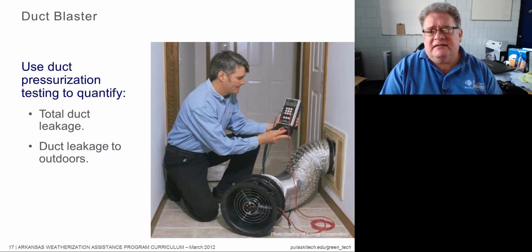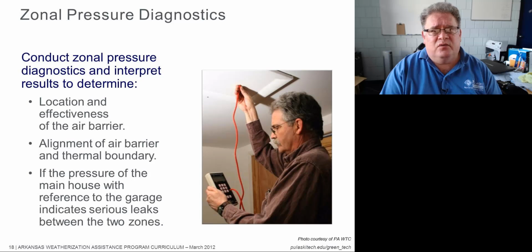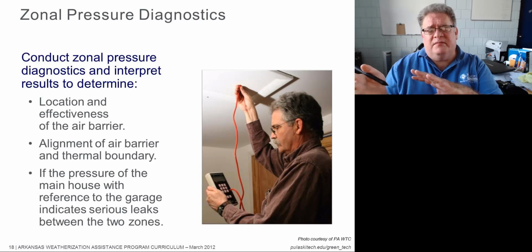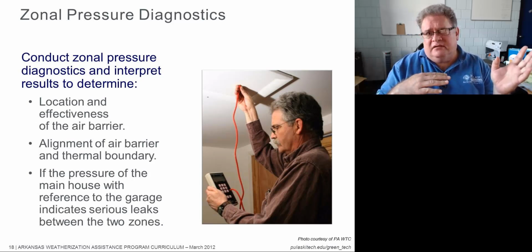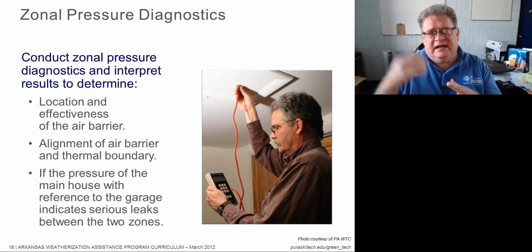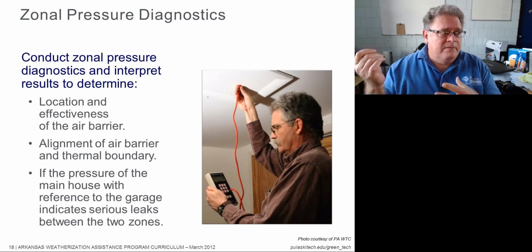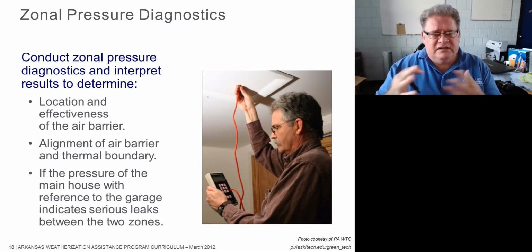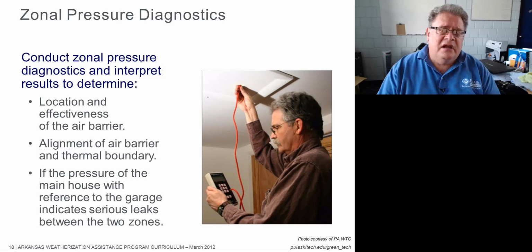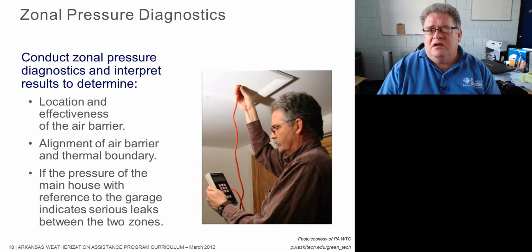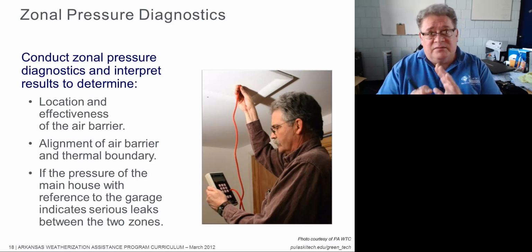Zonal pressure diagnostics. This is when we're testing an air barrier. We're conducting a pressure test from one side of an air barrier to the other. And generally the manometer stays on one side and we put the reference to the other side, or we put the input to the other side. It just depends on what's going on in the house. But really it tells us what kind of condition the air barrier is in. The reason we do this is so that we know whether the air barrier is where we expect it to be, or does it appear to be someplace else, or do we have multiple air barriers.